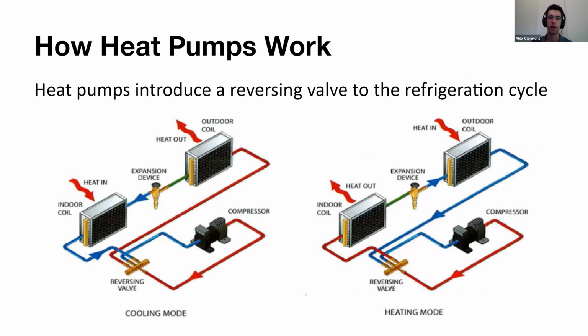Now, what is a heat pump? It's the same as your refrigeration cycle again, but you can reverse the flow. Your outdoor coil can turn into your evaporator, and your indoor coil can turn into your condenser. That's why you'll often hear Eric and I refer to the machine outside as the outdoor unit, as it's not always the condenser. It's only the condenser when the system is in cooling mode. In the winter, it becomes the evaporator.